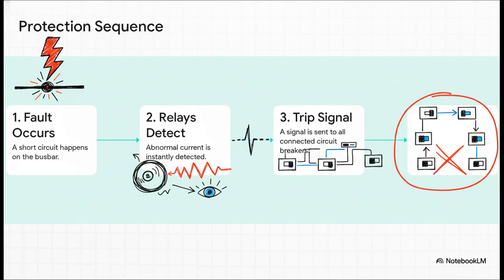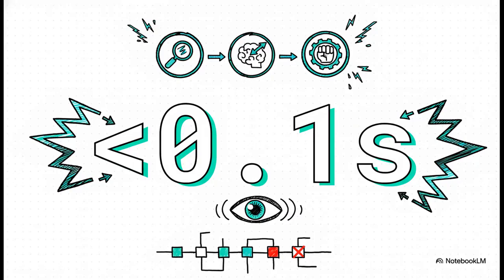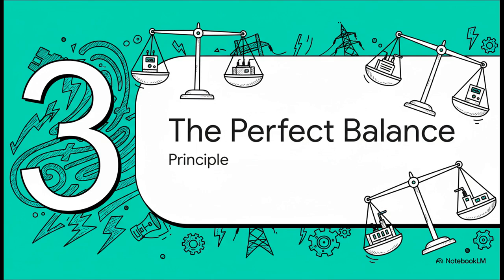So here's how it all goes down. First, a fault happens on the busbar. Second, the protective relays instantly, and I mean instantly, detect that something is wrong with the current flow. Third, they blast out a trip signal to all the circuit breakers connected to that bus. And finally, bam, those breakers fly open, completely disconnecting and isolating the faulty bus from the rest of the grid. And get this, all of that happens in less than one-tenth of a second. That is literally faster than you can blink your eye. The system detects the problem, makes a decision, and acts before the catastrophic damage can really even get started. It's incredible. So how in the world does the relay system make such a huge decision so incredibly fast?